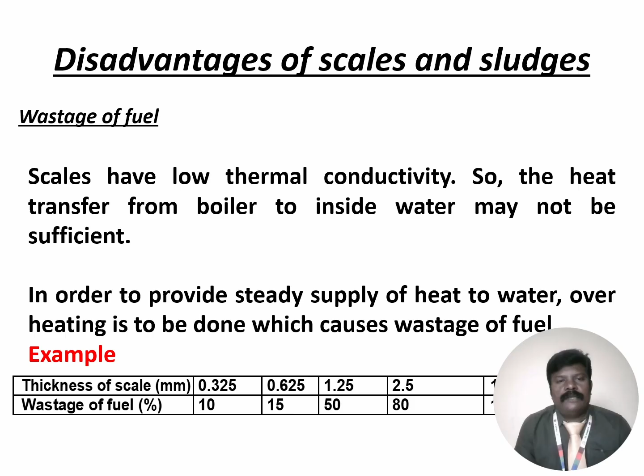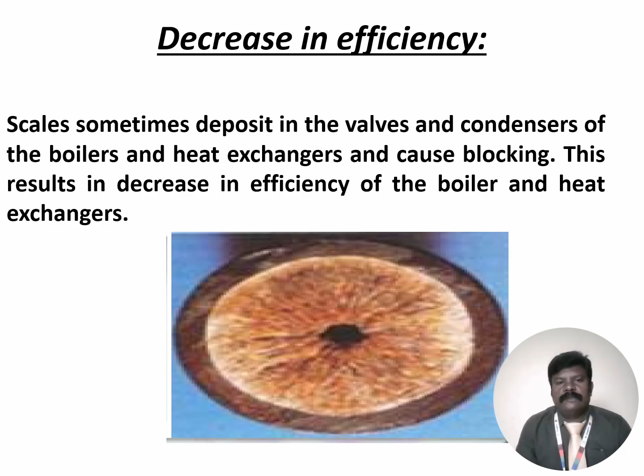Next drawback is a decrease in efficiency. Scale sometimes deposits on the walls and condenser of the boilers and heat exchangers and causes blocking. This results in a decrease in the efficiency of the boiler and heat exchanger. Here the scale formation is strongly attached on the boiler wall or the pipeline. They may block the water flow, which will not allow the water to pass efficiently.